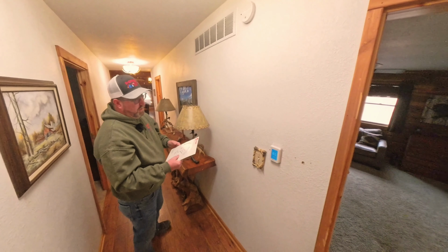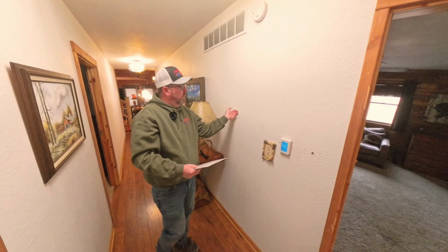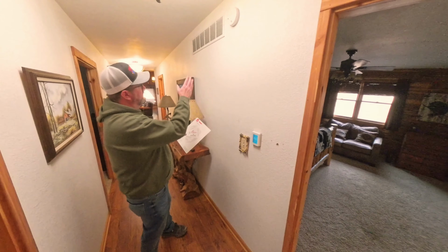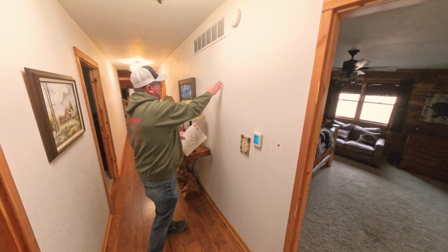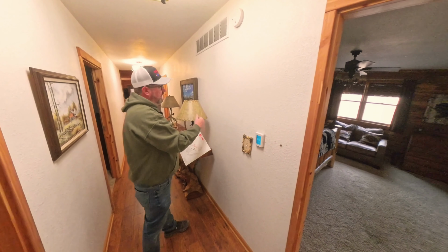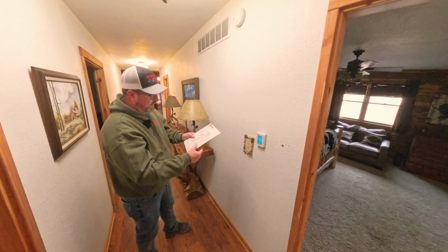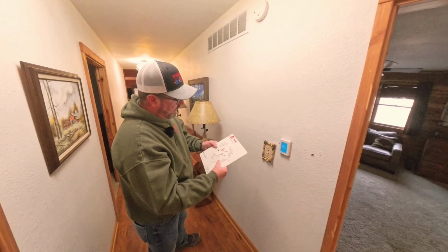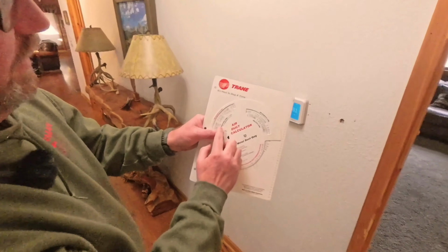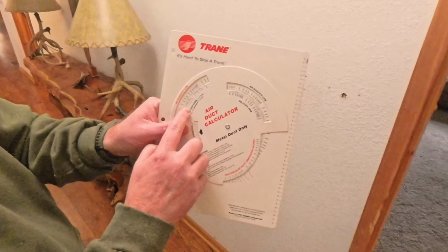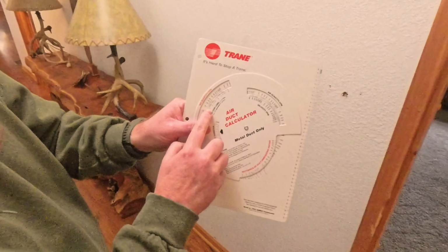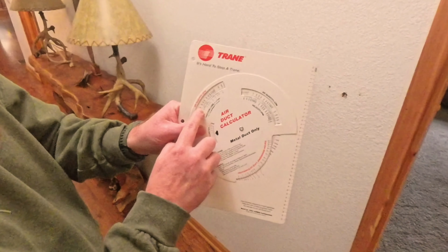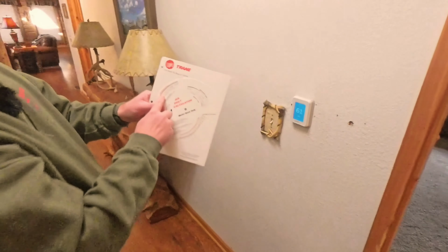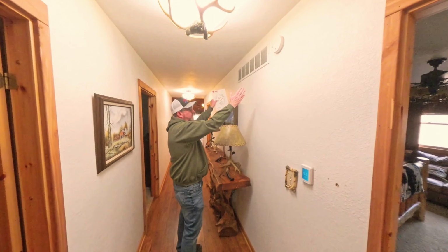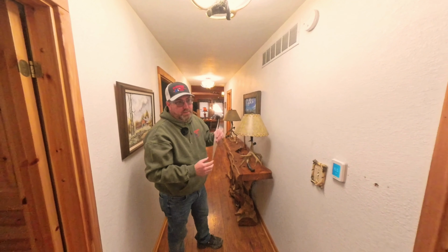And if we were to look on a duct calculator of a typical 2x4 wall, and we get to what one of these spaces is, it's 14.5 inches in between the studs, 3.5 inches wide. We put that on a duct calculator, and we look here at approximately 0.1. We'd like to see static pressures a little lower than that on the return side. We get about 150 CFM. So this one, what we call a double, would carry 300 CFM.